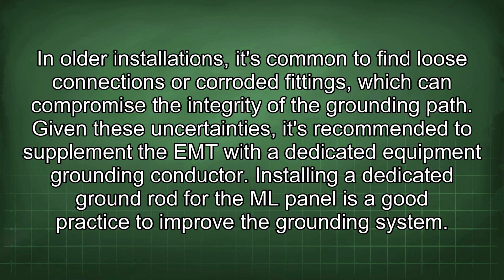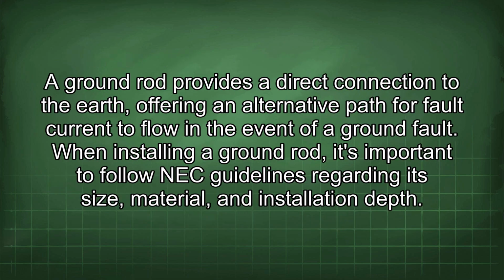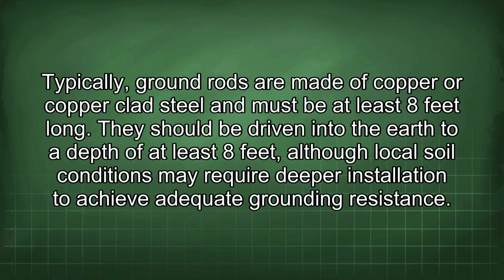Installing a dedicated ground rod for the ML panel is a good practice to improve the grounding system. A ground rod provides a direct connection to the earth, offering an alternative path for fault current to flow in the event of a ground fault. When installing a ground rod, it's important to follow NEC guidelines regarding its size, material, and installation depth. Typically, ground rods are made of copper or copper-clad steel and must be at least 8 feet long. They should be driven into the earth to a depth of at least 8 feet, although local soil conditions may require deeper installation to achieve adequate grounding resistance.